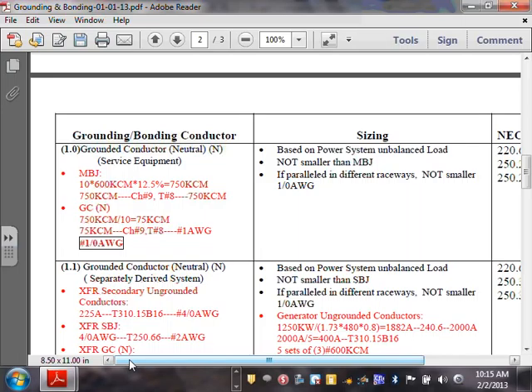Now, I know some of you guys have looked at my service are 600 amp and my neutral is 1 aught. A lot of engineers, guys, they go, if the service is one size, we go 2, 3 sizes and we size it and call it a day. But remember, this is the minimum size that you can pull. Can I go higher than that? Be my guest. That's your minimum size that you can pull. And I know a lot of engineers who take 600 amp, 600 kcm, 500. We have 400. Probably they will size it for 350, kind of half of what the service is, and call it a day, 350. But that's, remember, we're going by the bare minimum. Any comments, guys? Any questions?